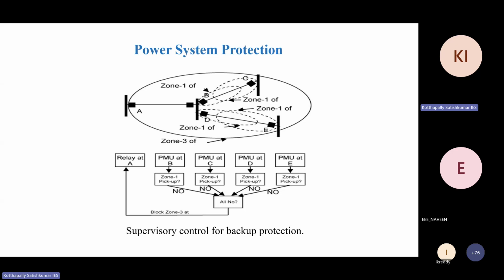The problem identified at that time was Zone 3 operation. Actually, Zone 3 should operate when Zone 1 protection has not operated. Here, for example, you have relays B, C, A and D. For B relay, Zone 1 is 80% of the BC line. For D relay, Zone 1 is 80% of the DE line. If Zone 1 fails, then relay A's Zone 3 will operate generally.